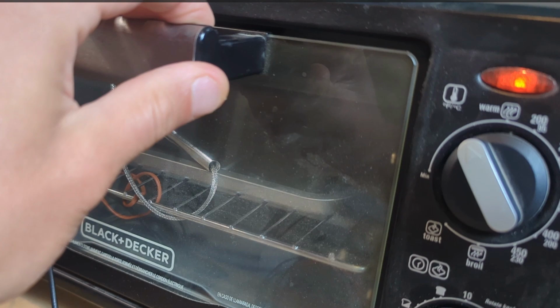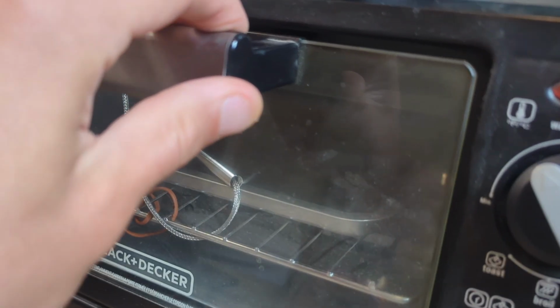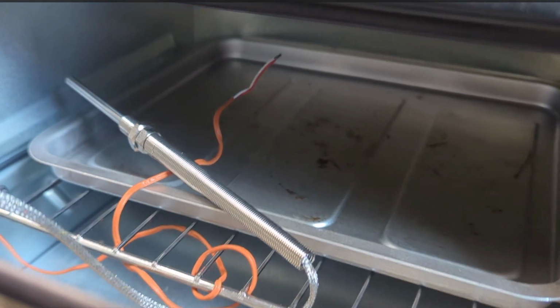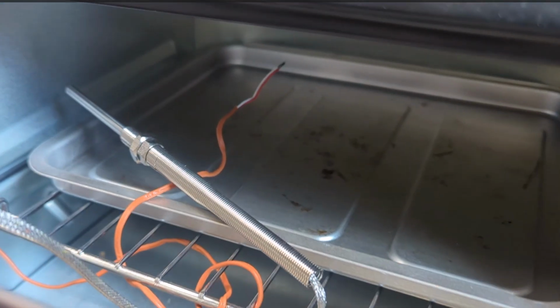So here's a video of our demo. What we're looking at is a toaster oven that Anabit uses for reflowing prototype boards. In there we have 2 thermocouple probes. We have a J-type that we normally use for monitoring the temperature in there. We have that connected to a data logger instrument, and we're just using that as a reference, so I'm not making things up, and the temperature is actually referenced to a known good temperature reading. And then the metal probe is the actual K-type thermocouple.